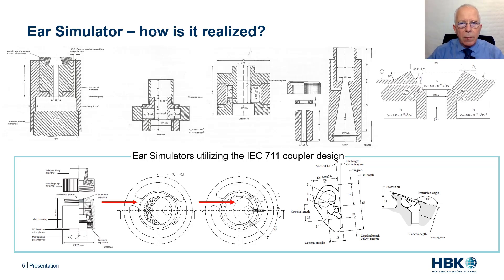Two examples of a simplified pinna simulator with controlled leakage are taken from ITU P.57 and are shown on the slide. To the left, a pinna simulator with high leakage, and to the right one with low leakage. The two different leakages are simulating a handset held loosely against the ear and a handset held firmly against the ear. In both cases, the 711 coupler is attached to the pinna simulator.